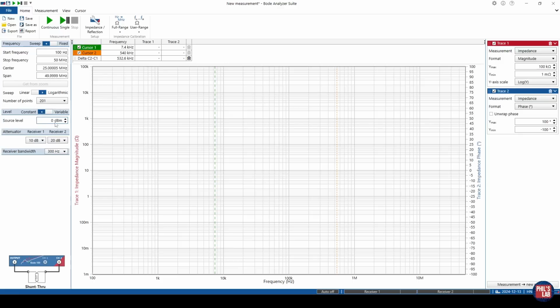So therefore, you want to adjust your source level so that it is high enough to maximize the signal-to-noise ratio, but not so high as to excite nonlinearities. And you can adjust the source level and check between measurements. If the measurement changes, your source level is probably too high.